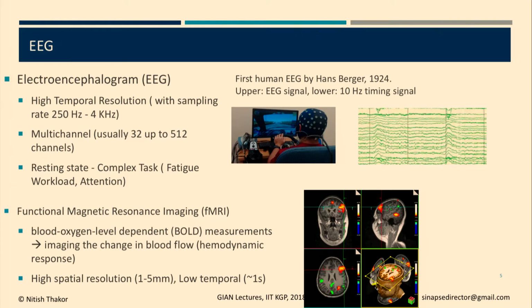The EEG it says 32 to 256 channels. Frankly, most people will get by with about 32 to 64, and you get pretty good information to produce networks and connectivity and so on. Those who want to do source localization, they need to construct the field. So, from outside sample, try to predict what is inside, and the more you have the better. If you have the full image of the brain and those 256 electrodes telling you a little bit of everything, it is easier, it is better mathematically to construct the source of activity like a seizure focus.